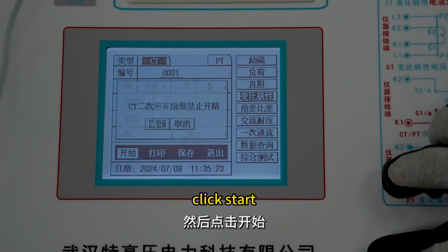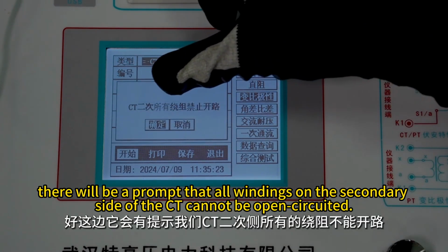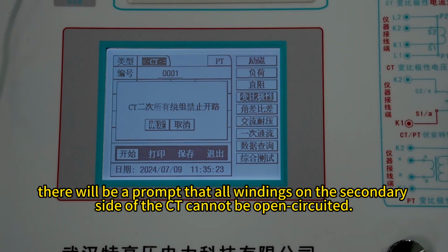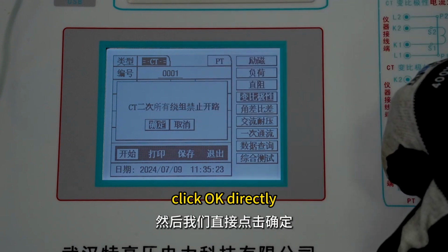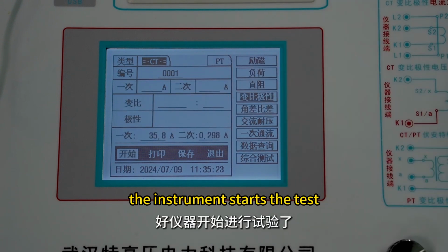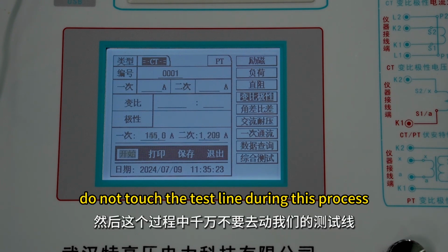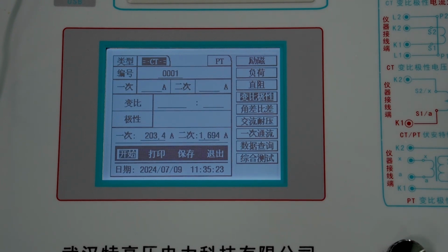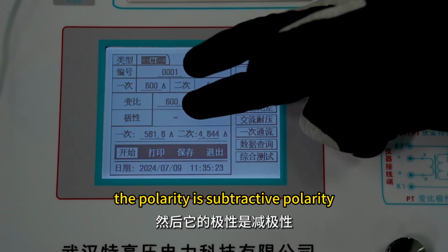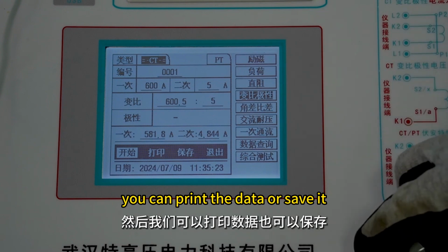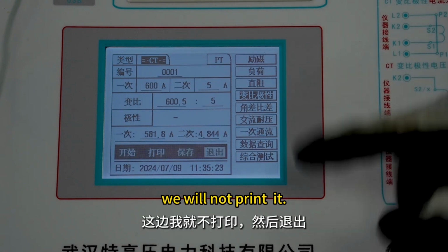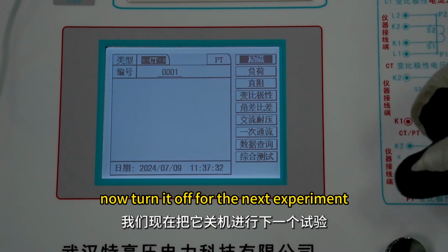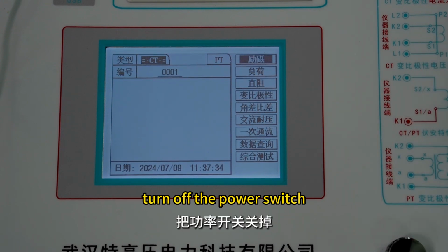Click Start. There will be a prompt that all windings on the secondary side of the CT cannot be open-circuited. We have just short-circuited them all. Click OK directly. The instrument starts the test. Do not touch the test line during this process. Its transformation ratio is 600:5. The polarity is subtractive polarity. The test is completed. You can print the data or save it. We will not print it. Exit. Now turn it off for the next experiment. Rewire. Turn off the power switch.